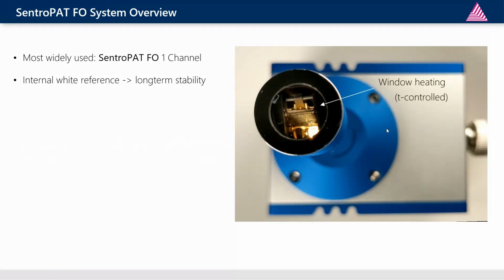The window can be heated and temperature controlled, which is beneficial in a couple of processes where raised temperature at the window reduces the risk of window fouling. The system has two built-in lamps, so it's possible to activate a second lamp without operator changing lamps on the system. The lamps are actually interchangeable. And these probes are ATEX certified for dust zone 20, zone 21, which is a requirement for quite a couple of these installations.